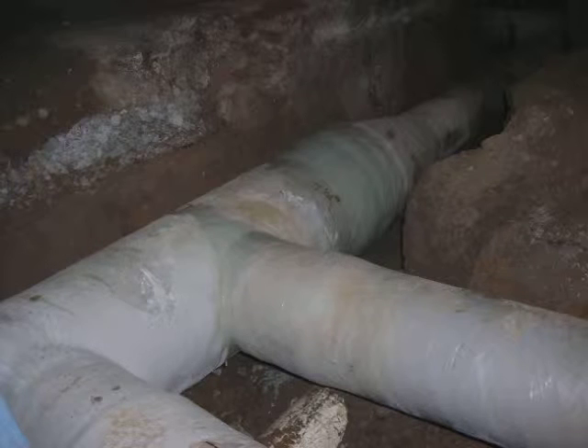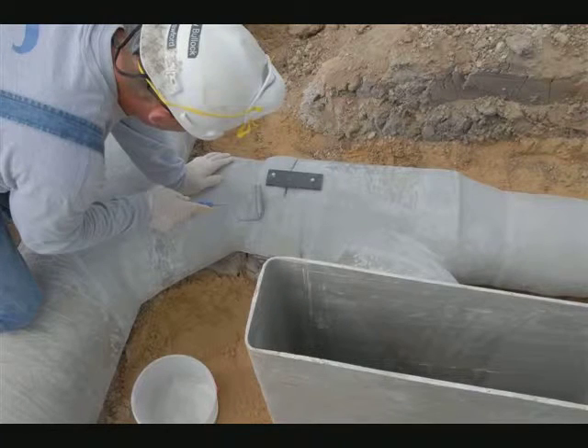One thing you have to do when you're burying the FRP underground is figure out where all your joints are. What we did was we had everything sloped in the bed of sand that the FRP was going to lay in. Then you lay out where all your joints are going to be, and we came in with a backhoe and took a pretty good scoop out where the joint is, so that you can get underneath the FRP to do your lap joints.